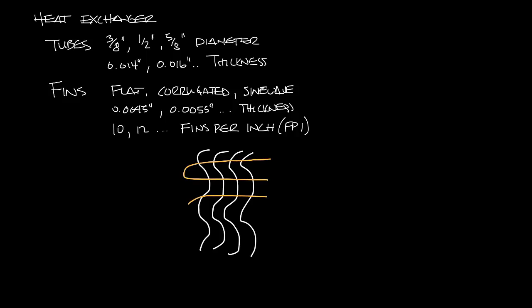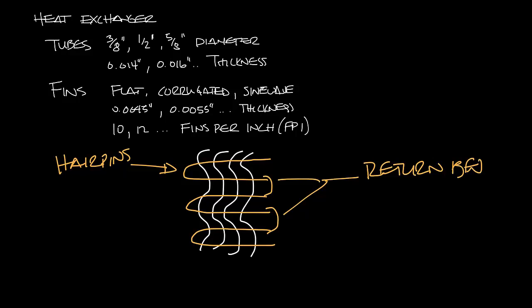The copper tubes are bent into hairpins and inserted through the fins. And then each hairpin is connected on the opposite side with a return bend that's welded on so that you get continuous flow of water through the tubes. And then on the ends you have your headers, also known as manifolds. This is where your supply and return water piping is connected to the water coil.